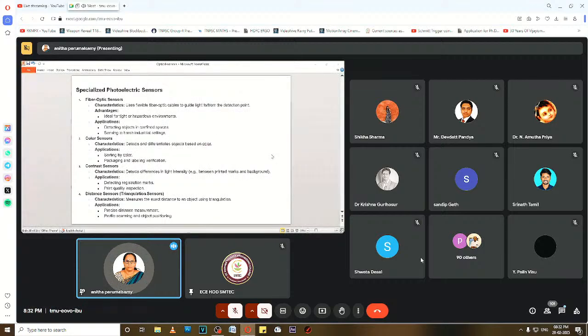Next is the distance sensor, also known as a triangulation sensor. It measures the exact distance between the sensor and the target object using the optical triangulation principle. This involves emitting a light beam, detecting the reflected beam's position on a receiver, and calculating the object distance. These sensors provide accurate distance measurements even in dynamic or complex environments.